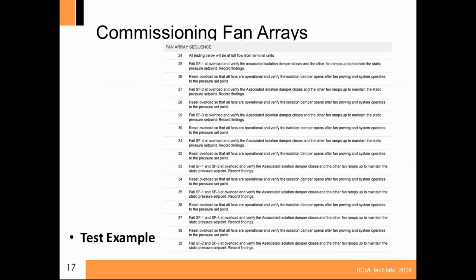This here is a test of another 4-fan wall, which I got carried away with, where I failed 1, and then I failed 2 individually and 3 individually. I don't recommend making a really complicated script like this. It's just a lot of time for you. In reality, you just need to do, arbitrarily on a 4-fan wall, fail any one, and then fail any of the other ones. You don't need to fail 1 and see what happens, restart 1 and see what happens, fail 2 and see what happens. You don't have to do that. Just do what you need to do with failing just 1 fan individually and another fan individually. In other words, don't test every fan.